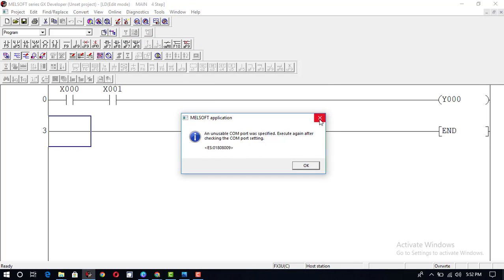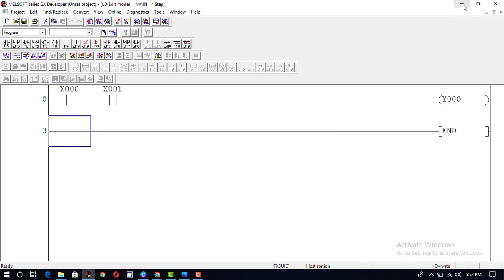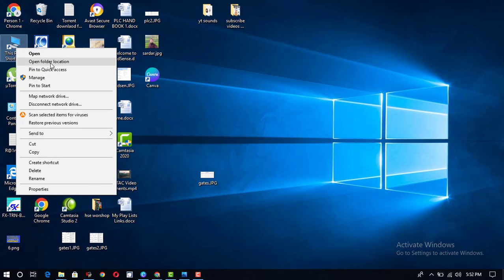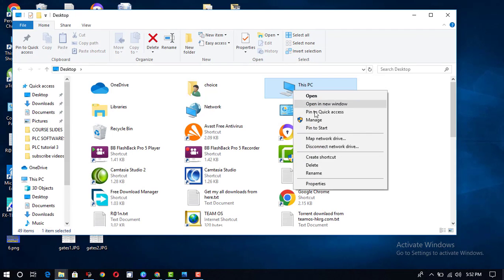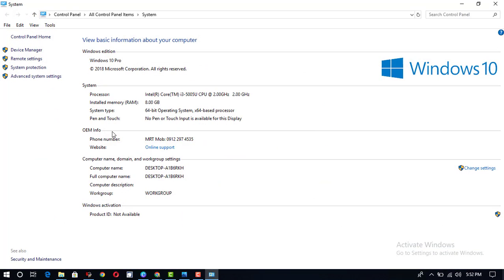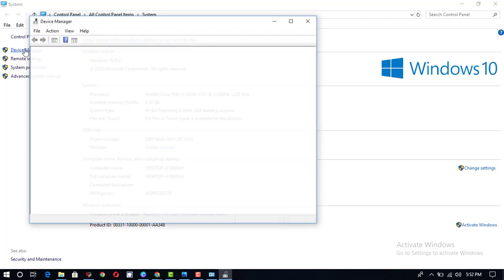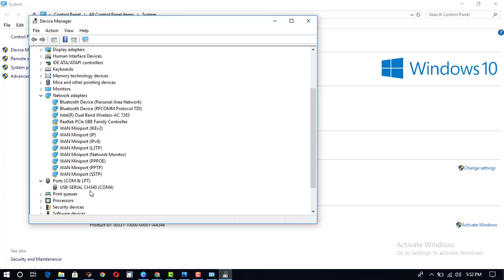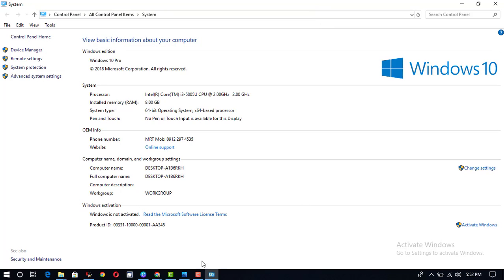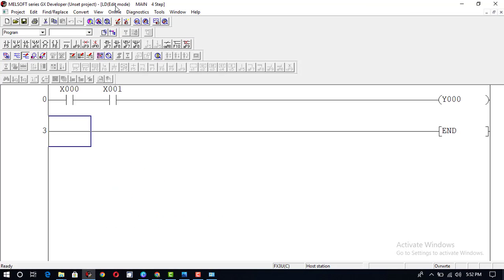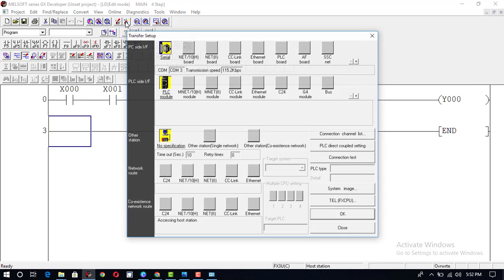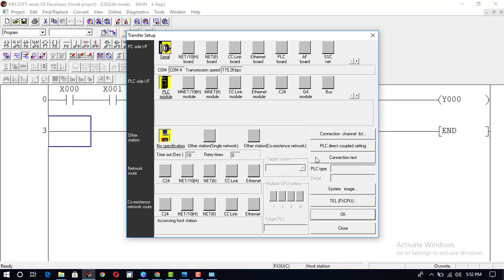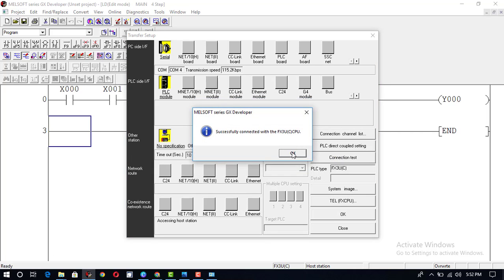The COM port is not selected, so first of all we will change its COM port. We will go to PC properties, then Device Manager, and check its COM port — it is COM4. So we need to change its port to COM4. We go to Online Transfer Setup and change the serial port from COM3 to COM4. The connection test is now successful and the port is OK.